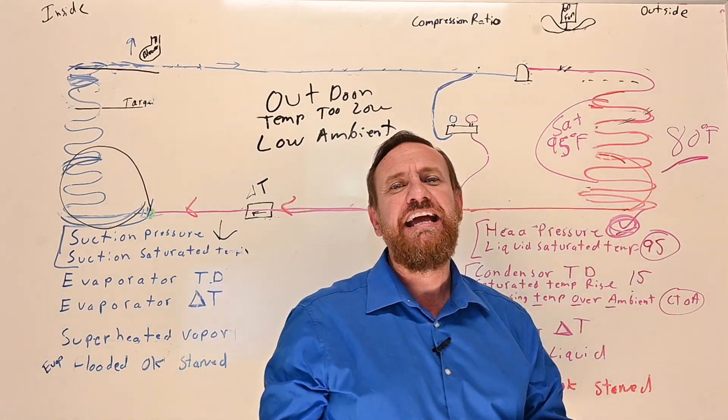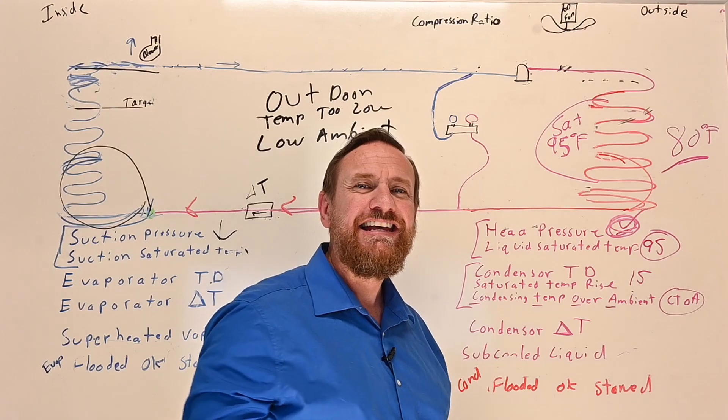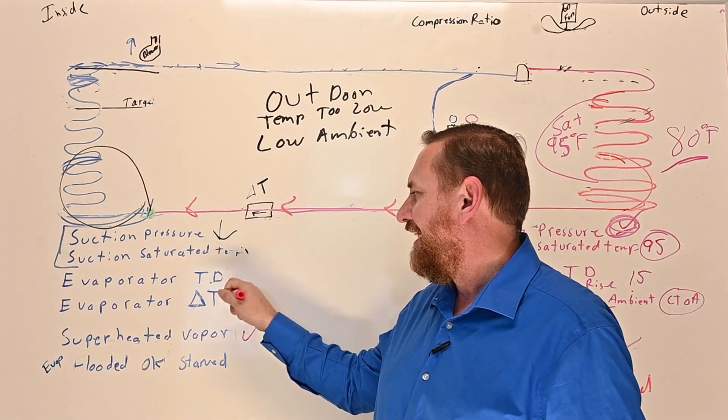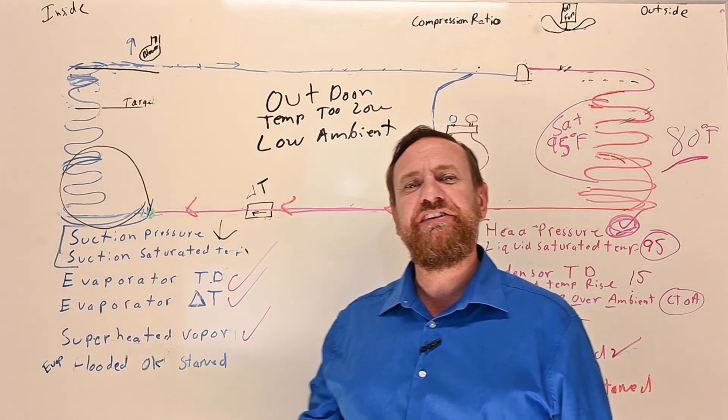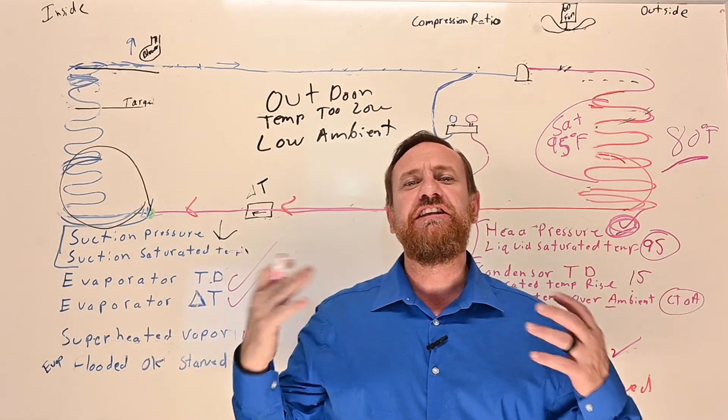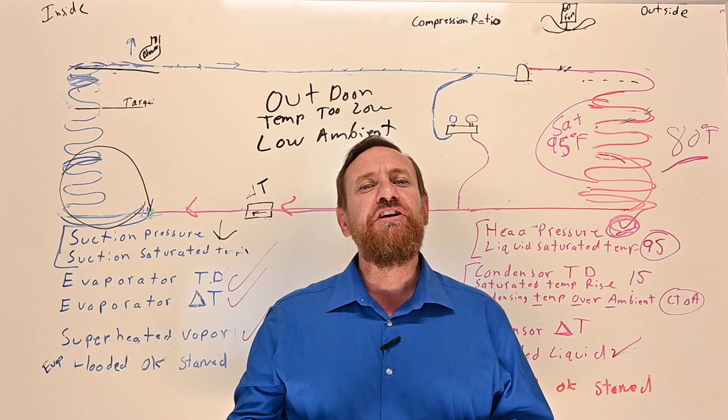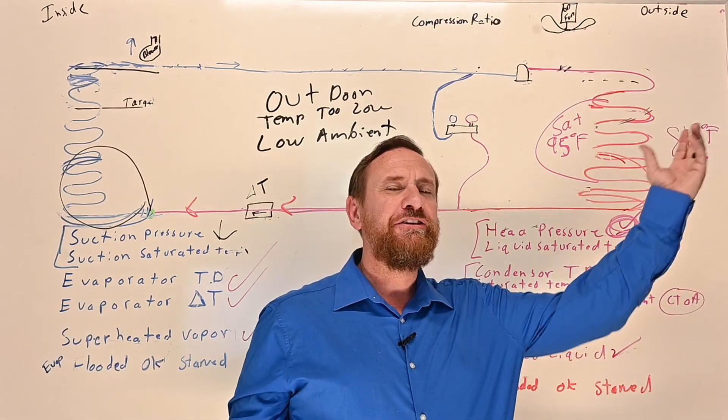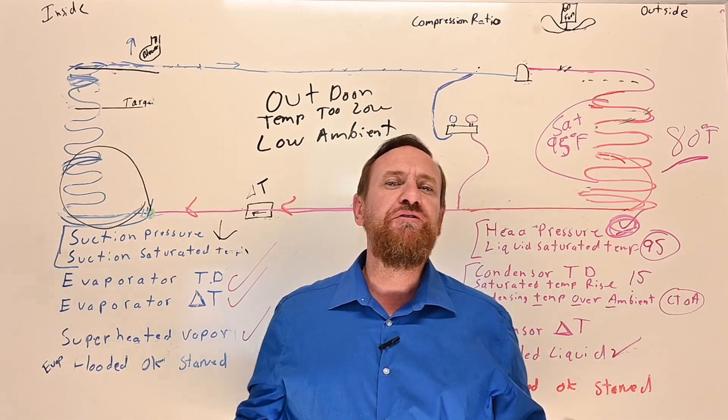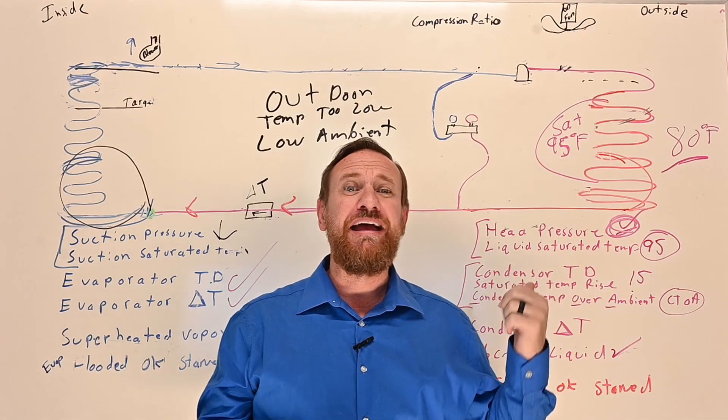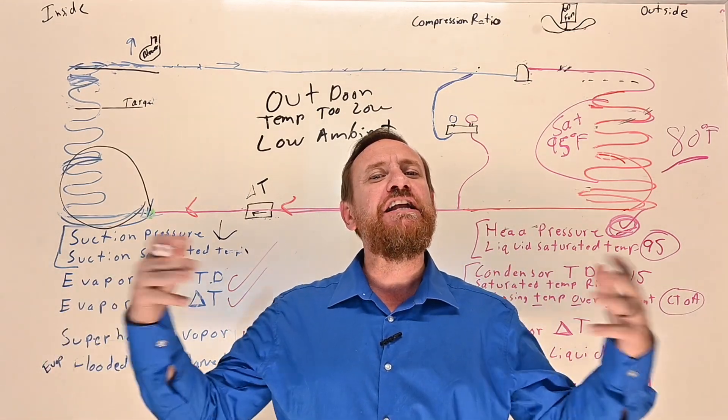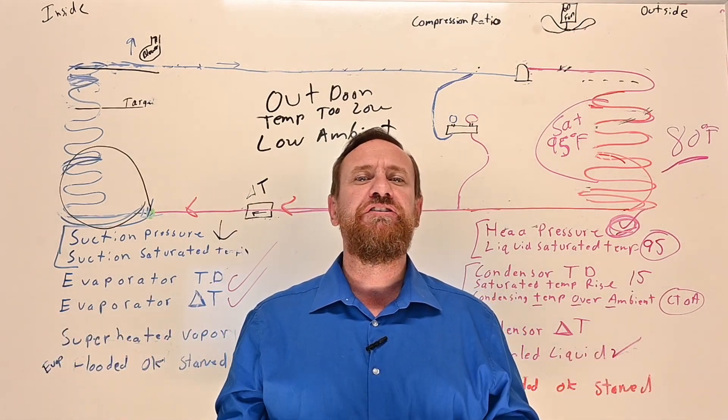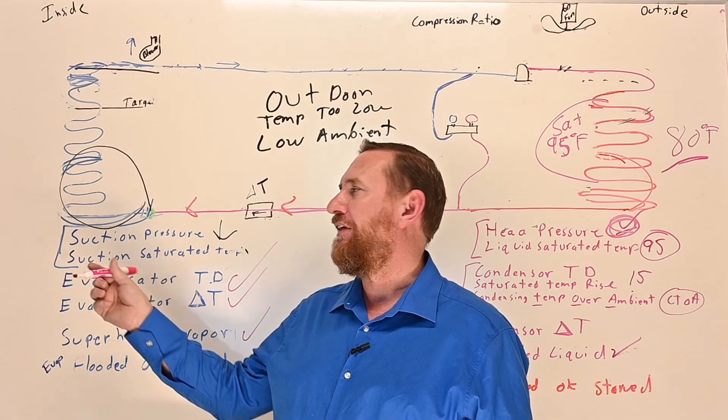So if I'm looking for a 95 degree saturated temperature, I convert that to a pressure. And all I got to do is simply block that condensing unit enough to try to keep it pretty close to a 95 degree saturated temperature. In that case, I know it's an 80 degree outdoor day. And then I can continue to check my sub cooling and my superheat and my evaporator TD, evaporator delta T, all these other numbers. I can check the entire rest of the system. But remember, you have a very small window to work with because you're taking the heat out of the house. Because the outdoor temperature is low, you're able to move heat very effectively with the refrigeration system. And on top of that, you don't have heat coming back into the house like you would in the summertime.